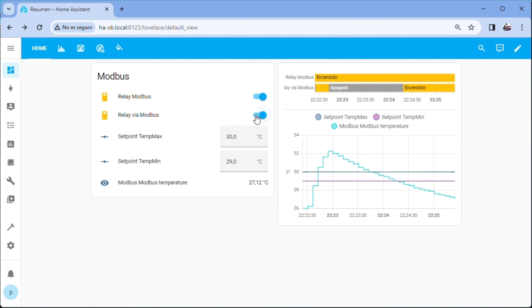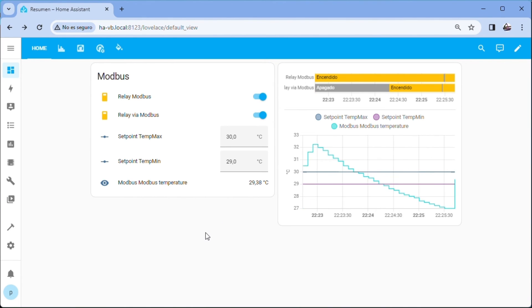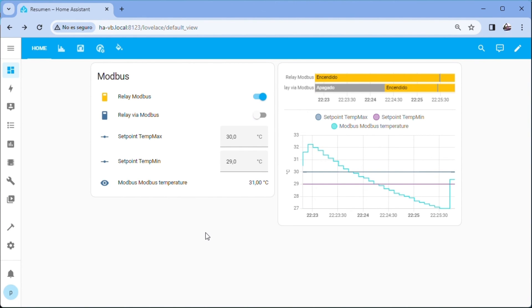We can do some tests with the switches. Changing the references or warming up the probe to see as the relay via Modbus stops when passing the maximum temperature and starts when going below the minimum.